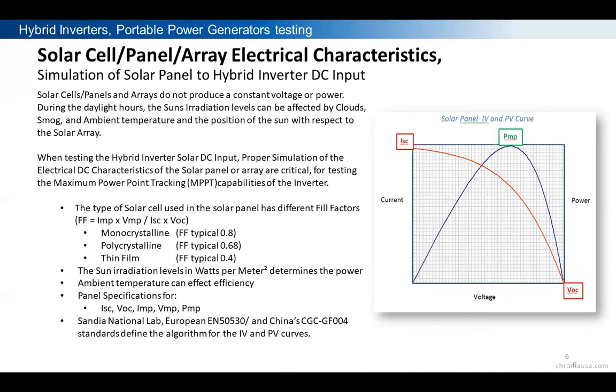When you're testing a hybrid inverter, you need to simulate that characteristic curve shown in this graphic. It shows that the unit can operate from an open circuit voltage at no load all the way up to a short circuit current. Along that curve, the blue line shows power versus voltage, and you'll hit a point where you get your maximum power. This is a critical characteristic of a solar array. We're going to talk about how the inverter tracks to determine maximum power and how that internal circuitry responds to this IV curve.